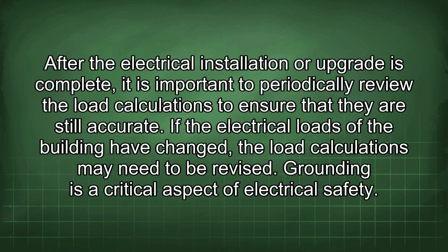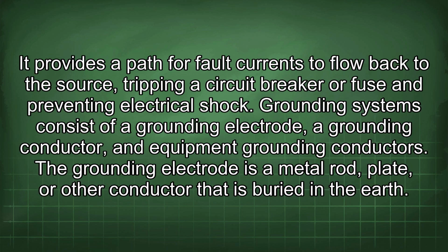After the electrical installation or upgrade is complete, it is important to periodically review the load calculations to ensure that they are still accurate. If the electrical loads of the building have changed, the load calculations may need to be revised. Grounding is a critical aspect of electrical safety. It provides a path for fault currents to flow back to the source, tripping a circuit breaker or fuse and preventing electrical shock. Grounding systems consist of a grounding electrode, a grounding conductor, and equipment grounding conductors.